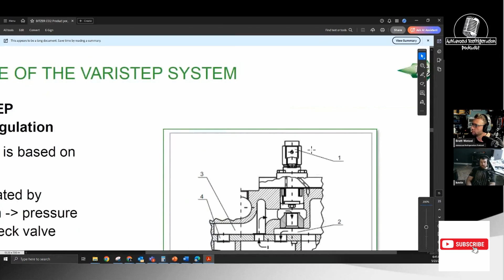I'm assuming this would be the suction side. So if this unloads, let me make sure, suction chamber number two. So when you get pressure on there, wherever it's pulling the pressure from, probably the oil, there's probably something internal in there, or from the discharge pressure, it pushes down on this when energized and essentially blocks off the suction.